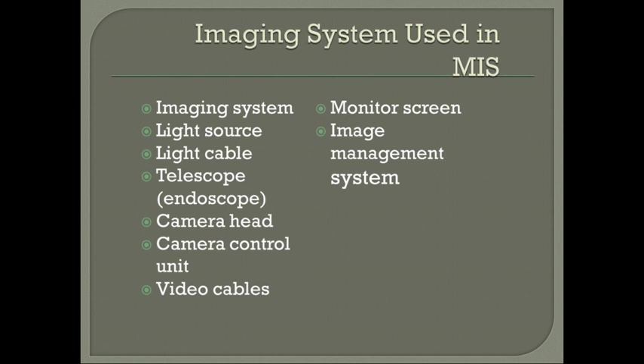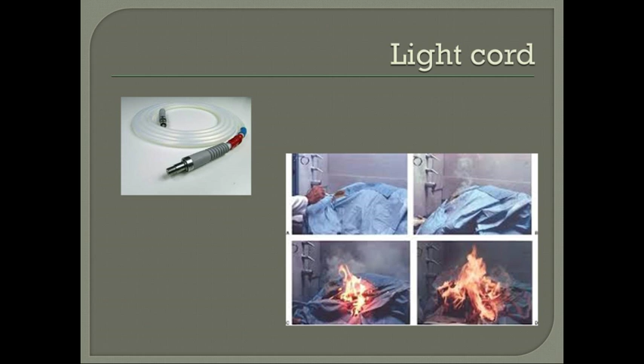As long as the light cord is connected to the scope, it does not get hot. But the light cord can catch the drapes on fire and should not lay directly on the patient. When you open the tray with the light cord, you want to visually inspect it for defects. You won't know if the light inside is damaged until you plug it in, and that's done sterilely.